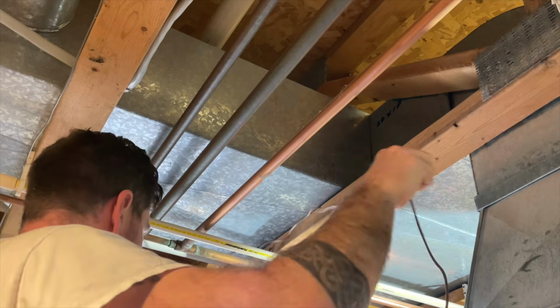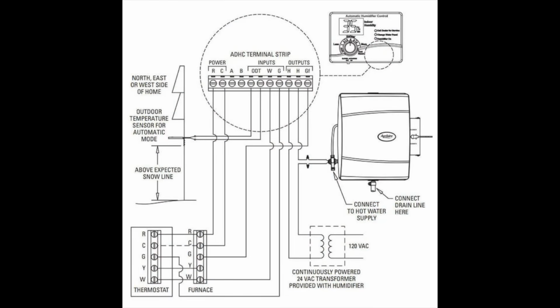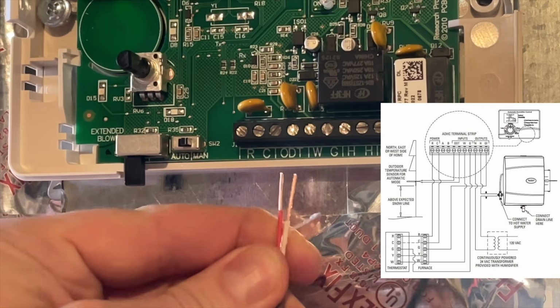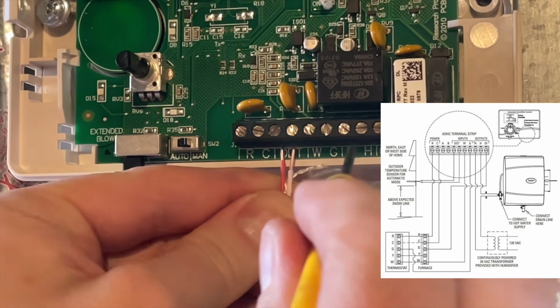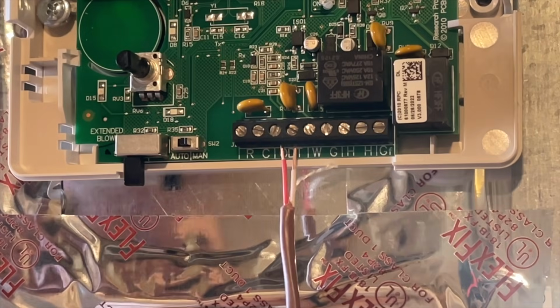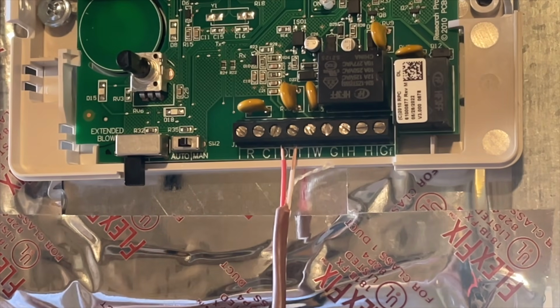Now, following the installation guide, we're going to start hooking up the actual electrical wiring, starting with the outdoor sensor, which hooks up to the humidistat on the ODT portion, with the red on the left and the white on the right, and then we tighten everything down with a small screwdriver.